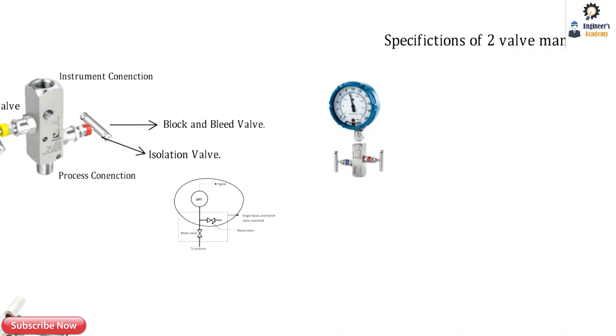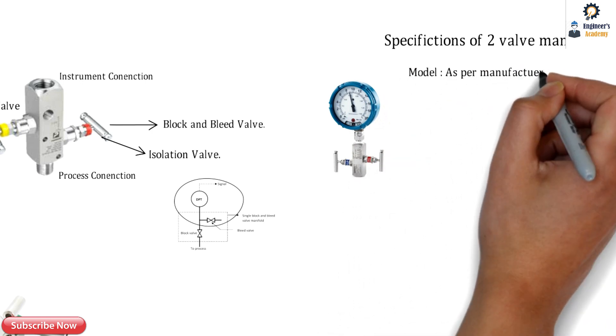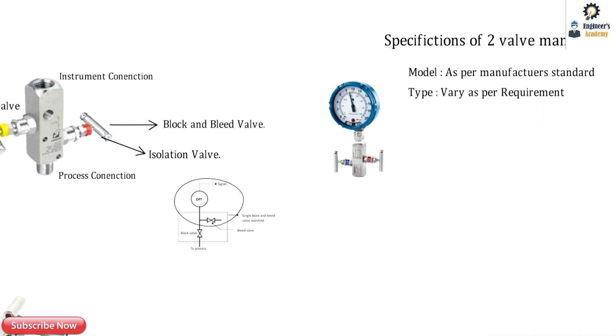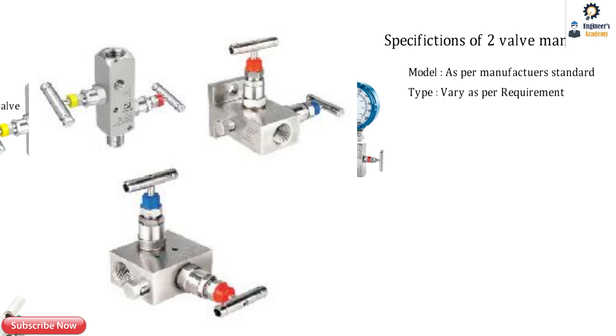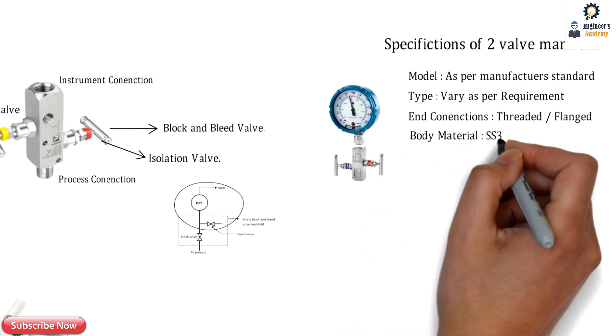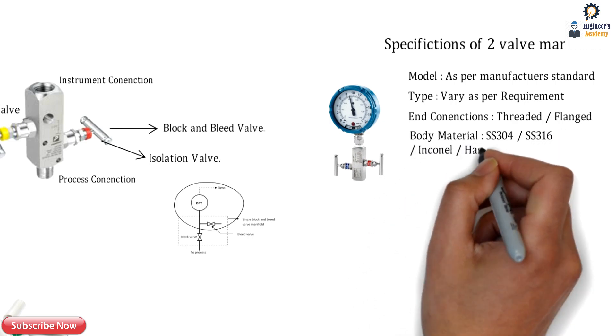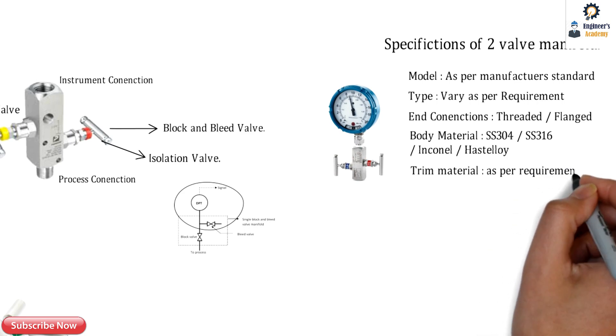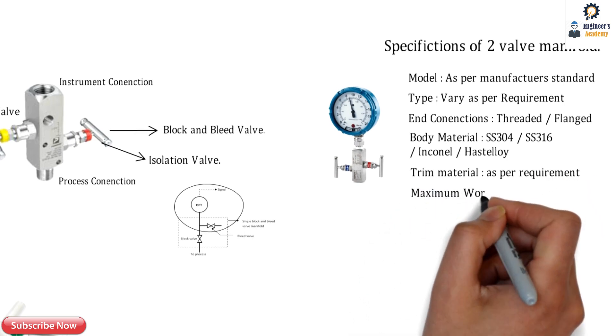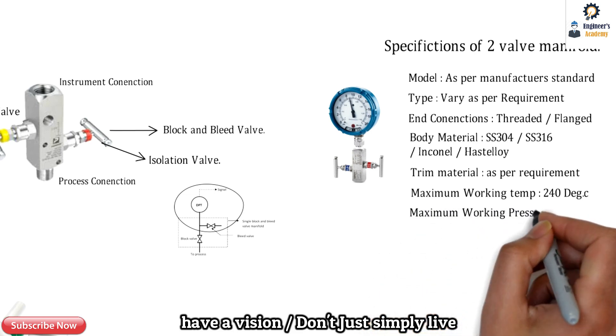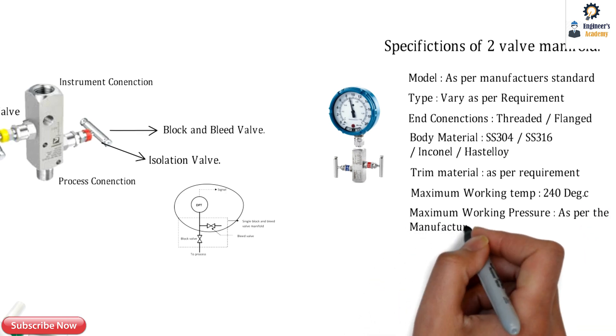For two-way manifold specifications: the model is as per manufacturer standard. The type varies per requirement and application — types include threaded, flanged, and female-by-female T-type manifolds. End connections can be threaded or flanged. The body material can be SS 304, SS 316, Inconel, Incoloy, Hastelloy, or other exotic materials. The trim material is as per requirement for wetted parts. The maximum working temperature is 240°C, and the maximum working pressure depends on the manufacturer's standards.